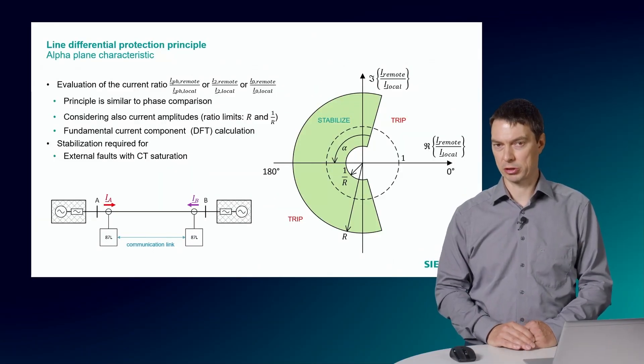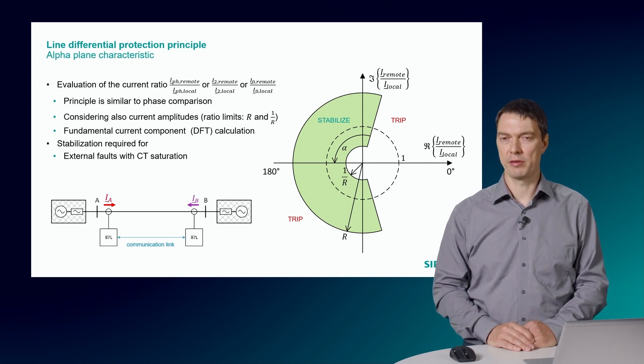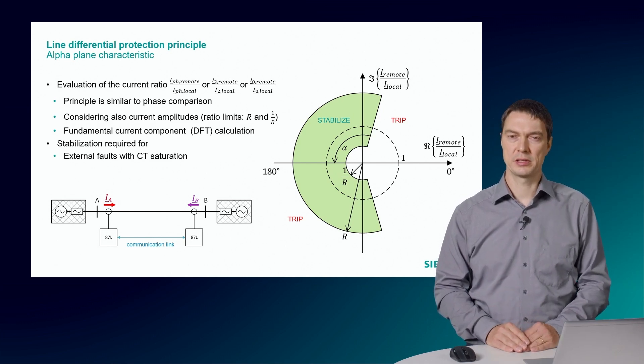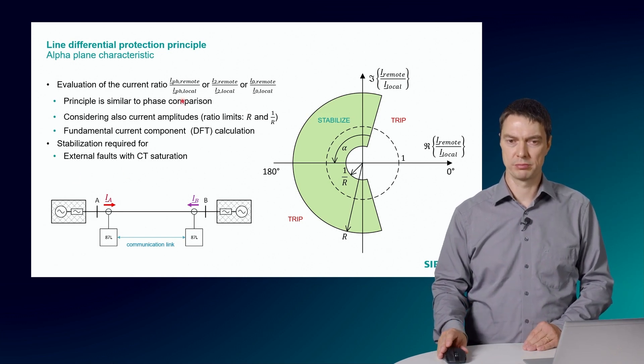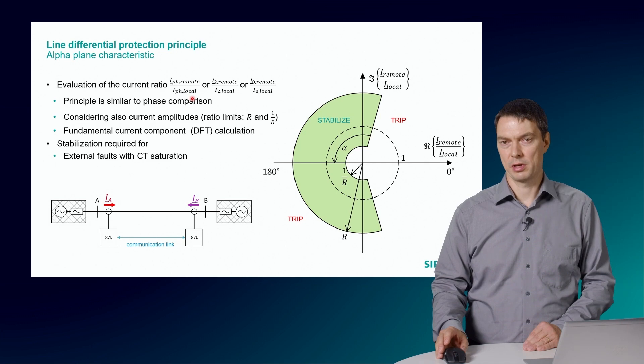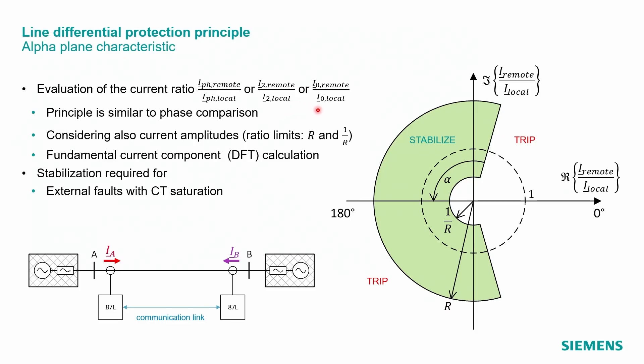An enhanced phase comparison principle, which also considers the current amplitudes, is a so-called alpha-plane characteristic. In addition to the evaluation of the phase difference, the ratio of the local and remote current amplitude is made. Phase currents and or negative sequence and or zero sequence phases are evaluated. For load or external fault conditions, both current magnitudes are similar in their value. The ratio is close to 1. This will result in a circle.